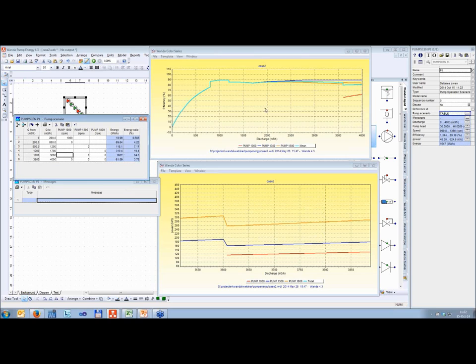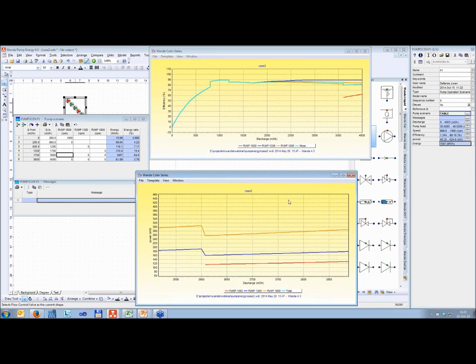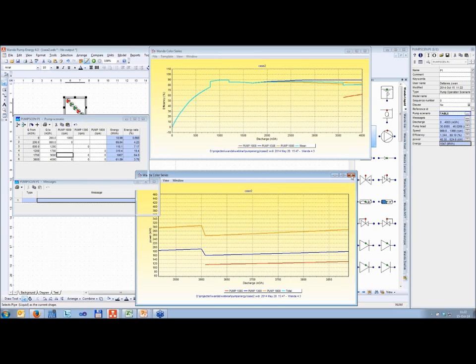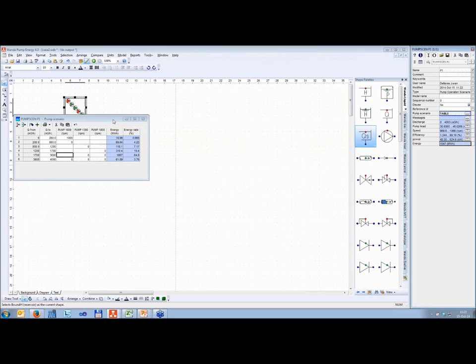So let's put that in — you cannot go any higher, that's the maximum. Based on that, we can say this is the optimized pumping scenario. We started with about 1750 megawatt hours and we are now at 1650 megawatt hours, so we saved about 100 megawatt hours. How much time did that take — 10 to 15 minutes? That's a quite good achievement. It's not that difficult to do and it can save you a lot of power. This is still a small example — you can easily go to bigger pumping stations and do the same, just optimizing your pumping schedule.